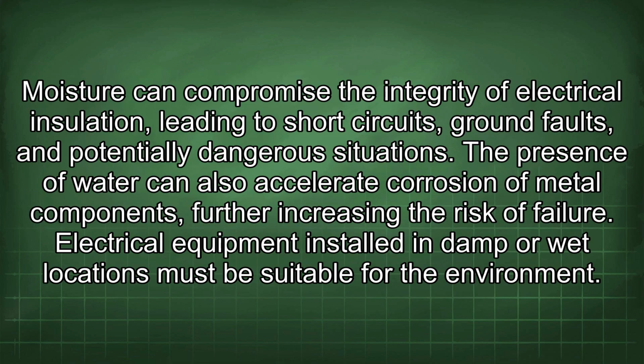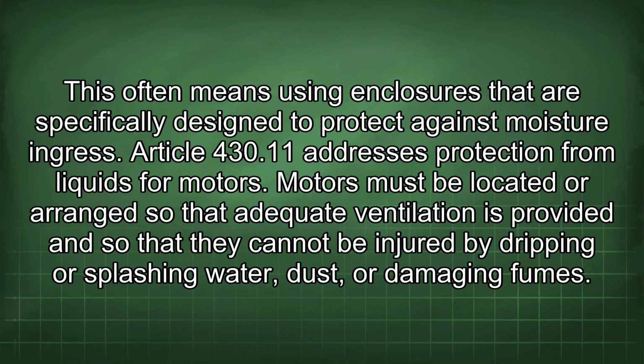Moisture can compromise the integrity of electrical insulation, leading to short circuits, ground faults, and potentially dangerous situations. The presence of water can also accelerate corrosion of metal components, further increasing the risk of failure. Electrical equipment installed in damp or wet locations must be suitable for the environment. This often means using enclosures that are specifically designed to protect against moisture ingress. Article 430.11 addresses protection from liquids for motors. Motors must be located or arranged so that adequate ventilation is provided and so that they cannot be injured by dripping or splashing water, dust, or damaging fumes.